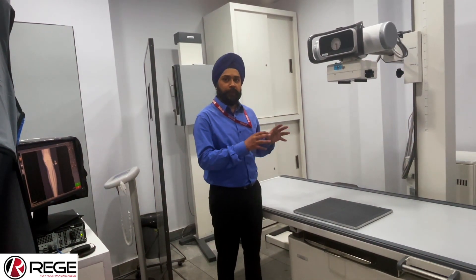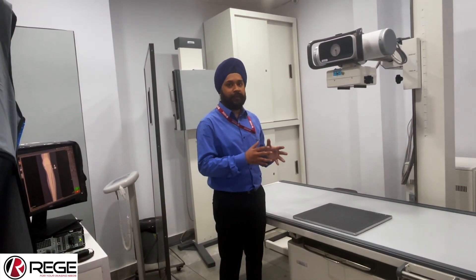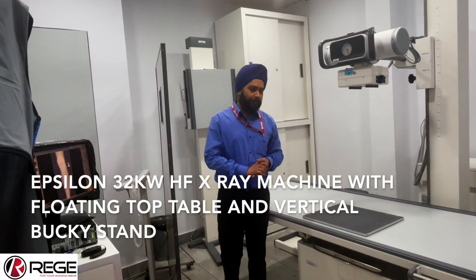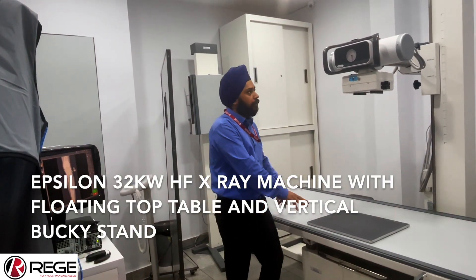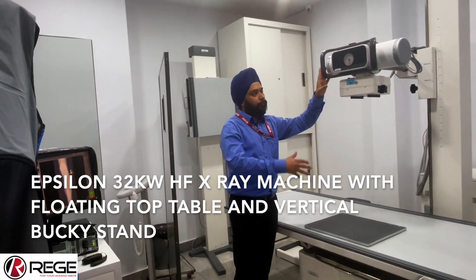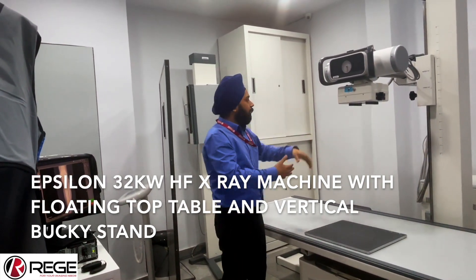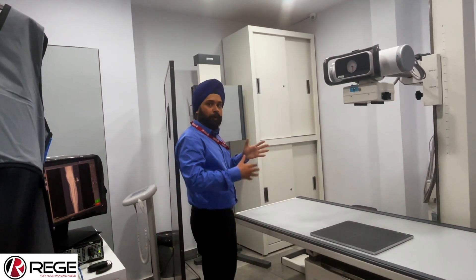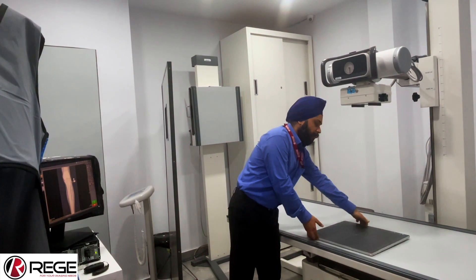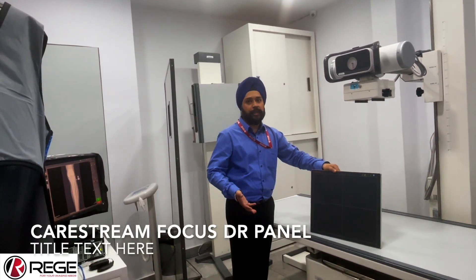Today we will show you a short demonstration of the Epsilon Healthcare 32 kW high frequency fixed X-ray machine. Briefly, this is the X-ray table — a floating top X-ray table. Here we have the X-ray tube which has up, down, right, left as well as telescopic movements. We also have a vertical bucky stand fitted with magnetic locks, and this is the Carestream Focus DR panel installed with these machines, which produces amazing image quality.